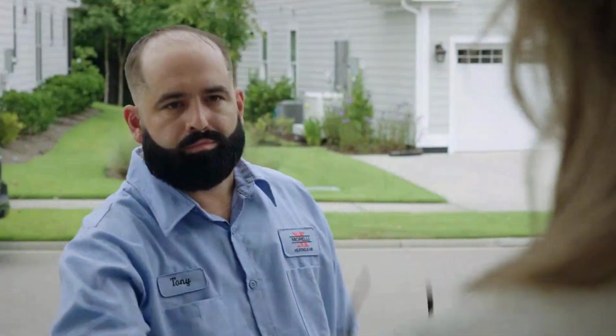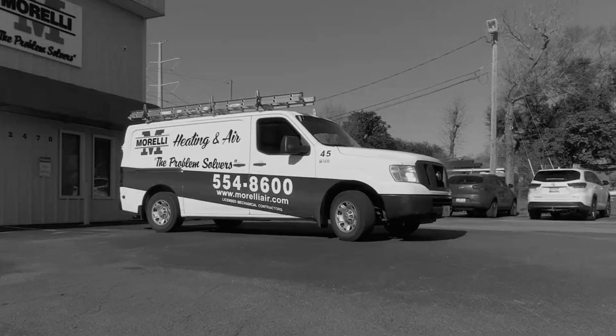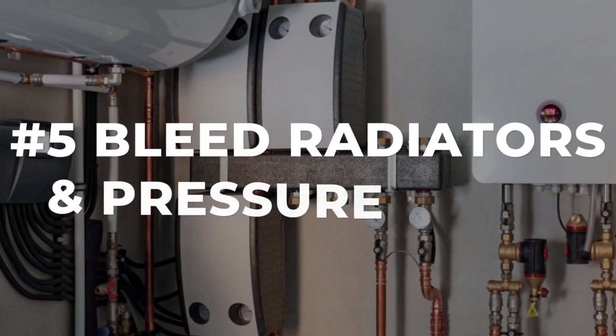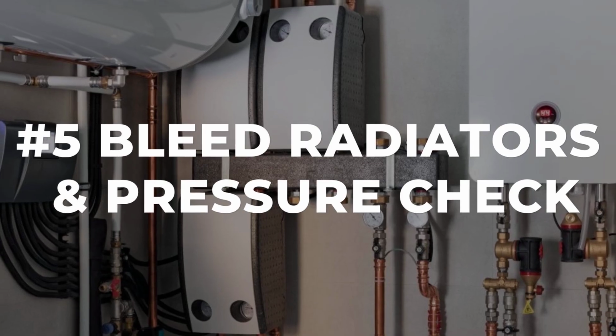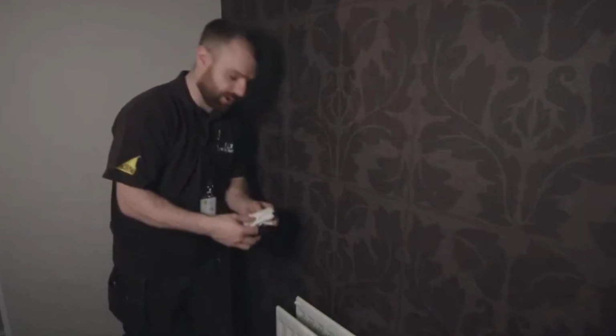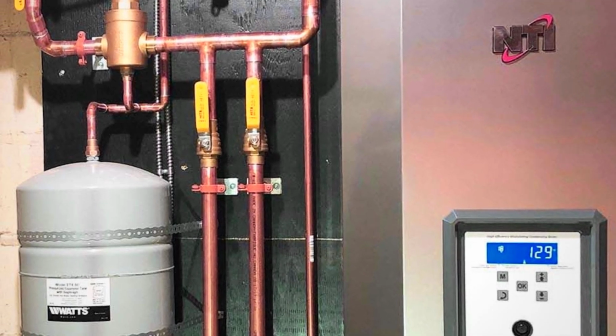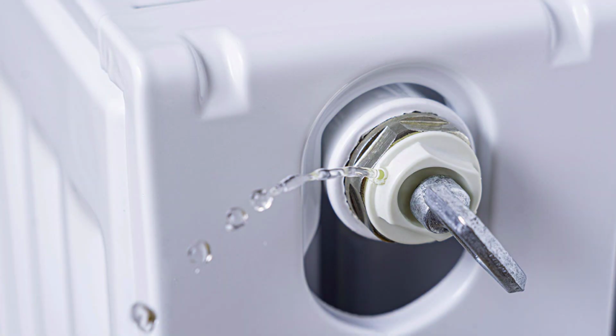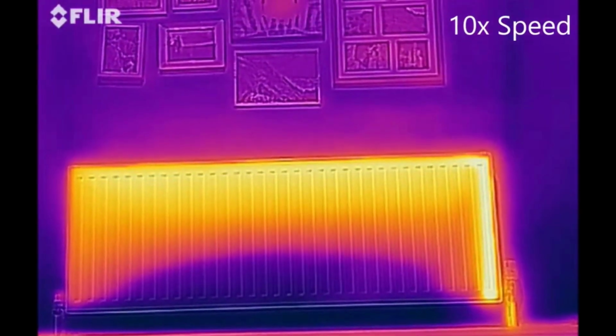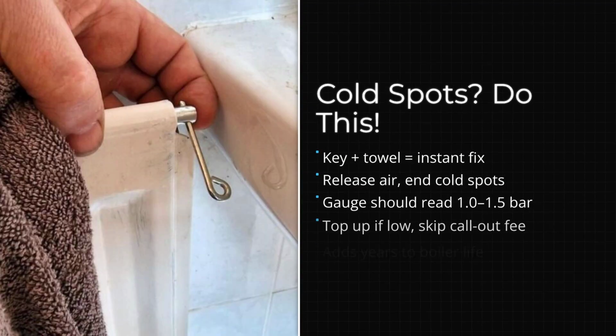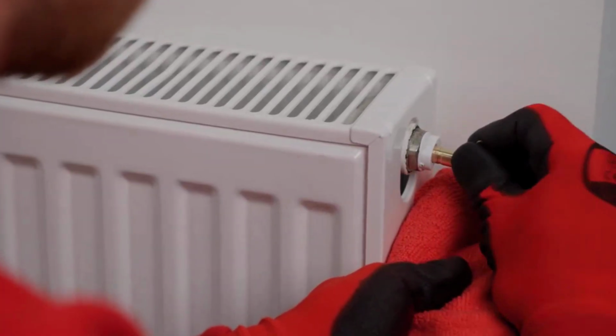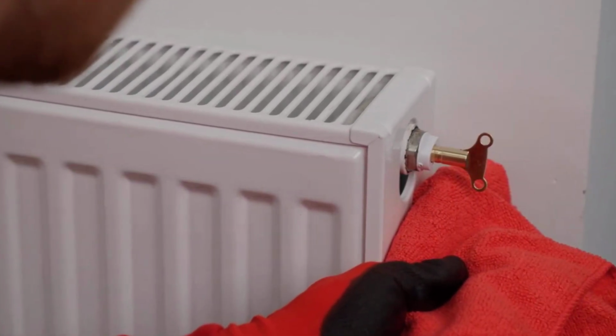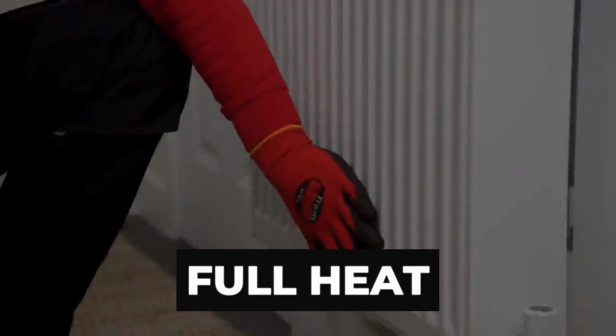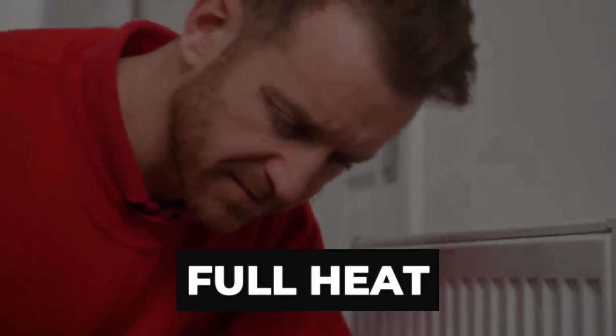In 5th place, nothing exposes the HVAC industry's replacement racket faster than the simple act of bleeding your radiators and checking system pressure. Cold spots at the top of a radiator or that telltale gurgling sound are not signs of a dying boiler. They are just trapped air choking your system's efficiency and driving up your bills. All it takes is a radiator key, a towel, and 10 minutes of your time. Crack the bleed valve at the highest radiator, let the air hiss out until water flows steady, and you have just restored full heat flow for free.